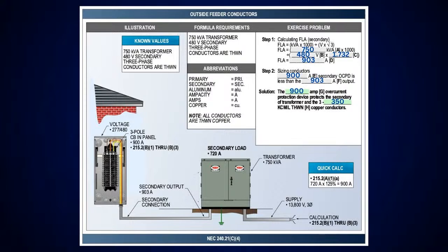This one's a 750 kVA transformer. You got 480 volts times 1.732. I think that's like 831 volts. I'll divide that into it. That's going to give you 903 amps. Now, this is an interesting one. Why can I go to a 900 amp overcurrent device and not? Because you drop down. That's right. Because of 240. That's why we do these different calculations, to make people think. Because if you go look at 240.4(C), anything over 800 amps, you can't exceed the calculated load of the conductors. Therefore, I drop down to the next standard size, which is a 900 amp overcurrent device. Nice. And isn't that interesting?